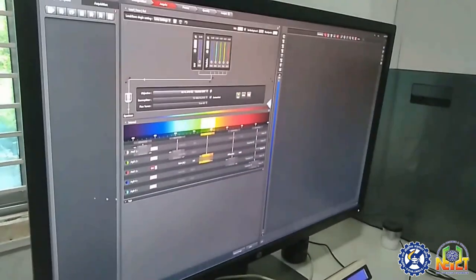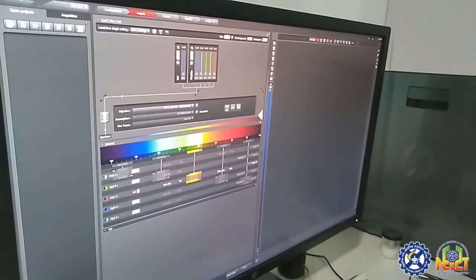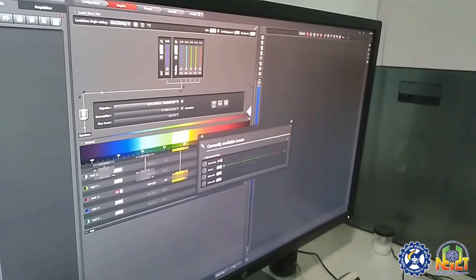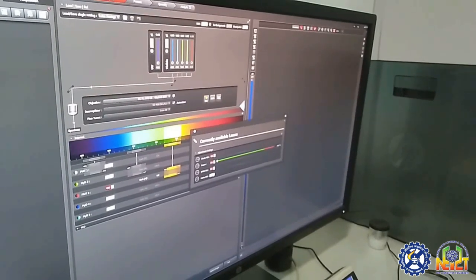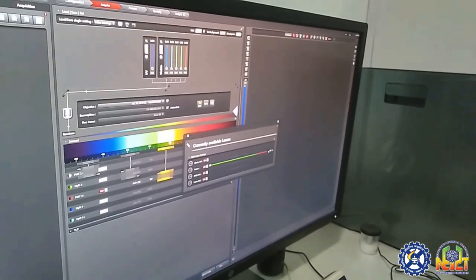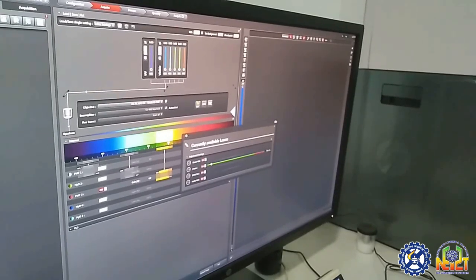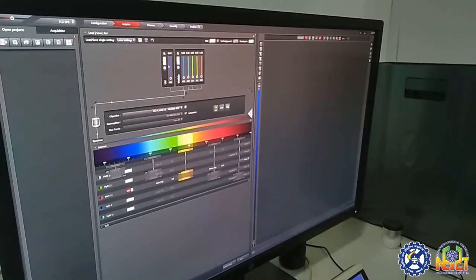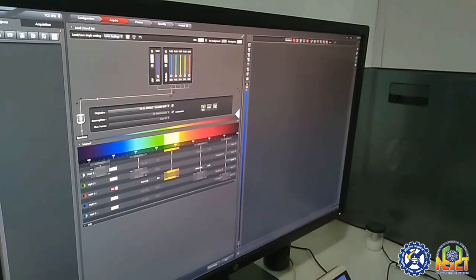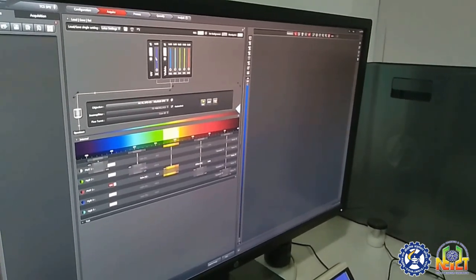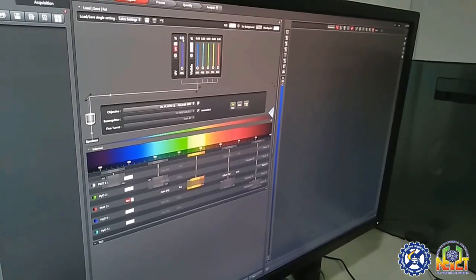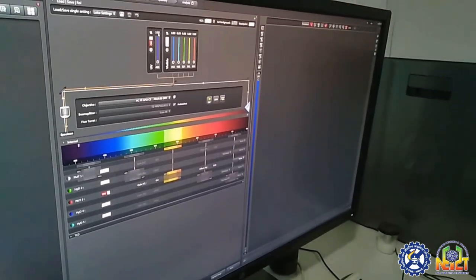Once I open this application, I am going to turn on all the lasers as per our requirement and set the value to around 5. Since my sample has DAPI stain, it needs excitation at 405 nanometers, so I am going to turn on the UV laser and set the value to around 3.